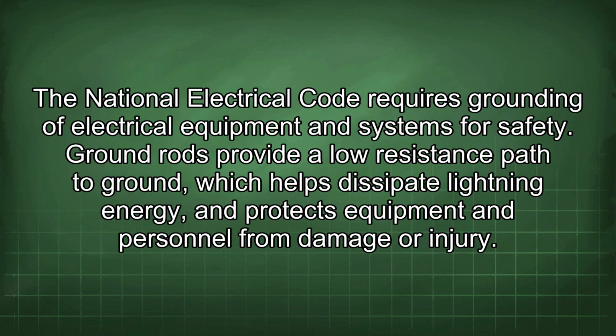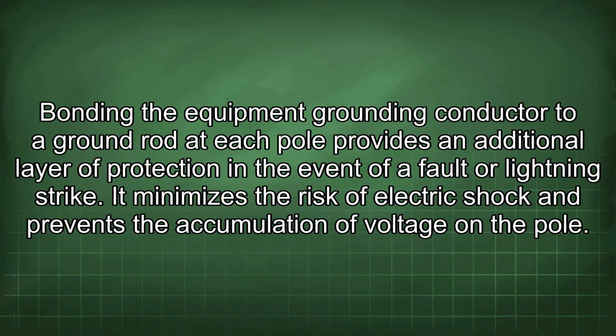The National Electrical Code requires grounding of electrical equipment and systems for safety. Ground rods provide a low-resistance path to ground, which helps dissipate lightning energy and protects equipment and personnel from damage or injury. Bonding the equipment grounding conductor to a ground rod at each pole provides an additional layer of protection in the event of a fault or lightning strike. It minimizes the risk of electric shock and prevents the accumulation of voltage on the pole.